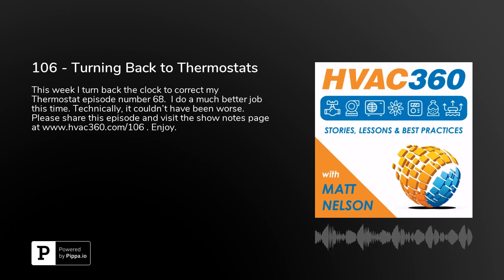So usually when you're in the heating mode, it'll cycle between 70 degrees, which is the set point that you set, and the offset, which is 68. So it turns on at 68 and goes to 70, because primarily the room in that mode is typically cooling off. So it's cooling off, you're heating it up a little bit, you're letting it cool off. What you don't want to have happen is, if you set it at 70, simultaneous heating and cooling, where it just wouldn't know what to do. So that's why you have this deadband.